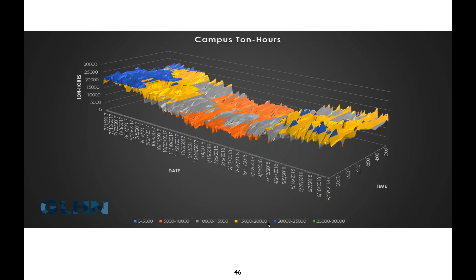If you look at the volume under this surface, what's underneath it is the total amount of ton hours, the total cooling load we're pulling out of the campus over the course of a year. That correlates almost directly into the campus water utilization. Every ton hour here represents 2 gallons of water. It's a bit simplified, a little more complicated than this, but fundamentally that's how we get to, of the university's 550 million gallons a year, the cooling towers consuming almost 300 million of it.